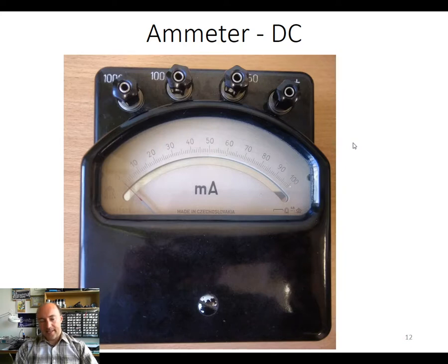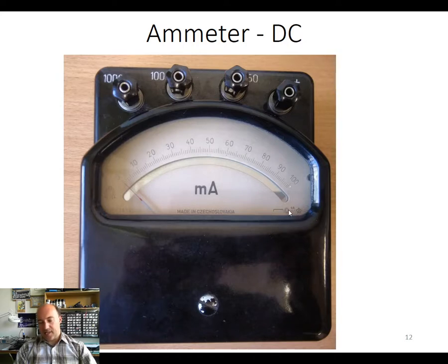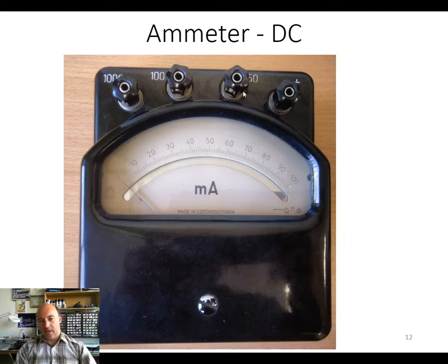The last analog instrument we will discuss is the ammeter — an instrument used to measure current. On the scale you can read the position, the accuracy class, and the system. This is a DC ammeter with 100 divisions on the scale. Here you can see the positive terminal and the different terminals for different ranges. This instrument does not have a knob to change the range; you need to manually reconnect to a different terminal if you want to measure a different current.